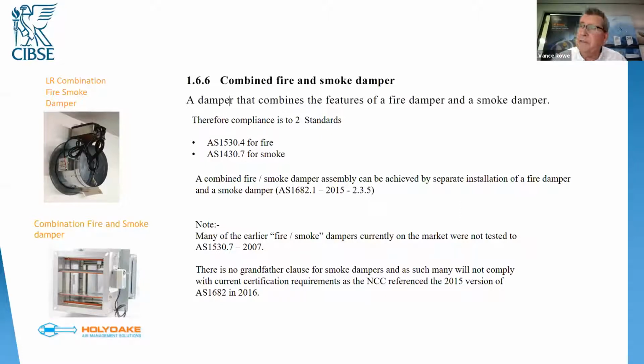I see that there's an error in my slide there. We will get that sorted out. I do apologise for that. So a combined fire smoke damper assembly, right, must be compliant with those two testing standards, right? And it is possible to use a fire damper and a separate smoke damper to achieve a fire smoke damper assembly.